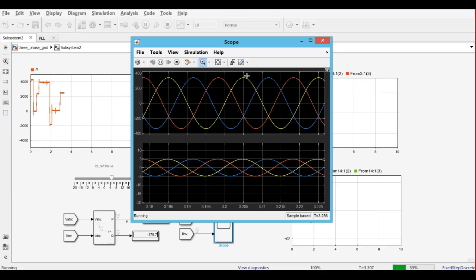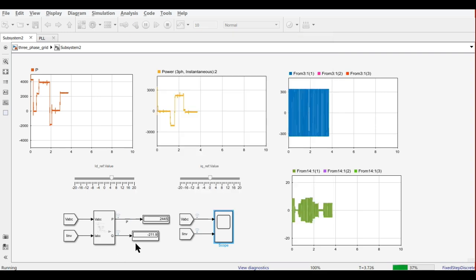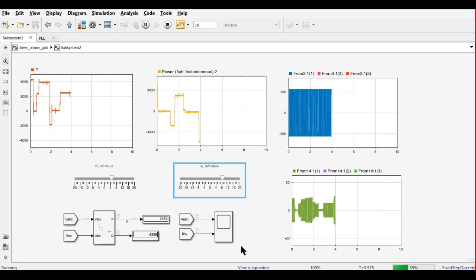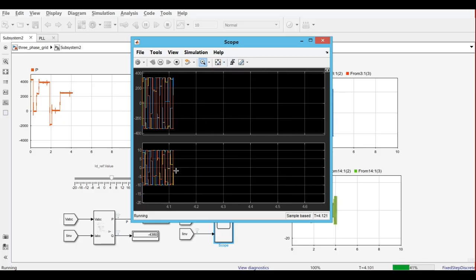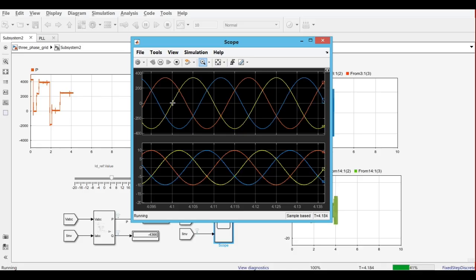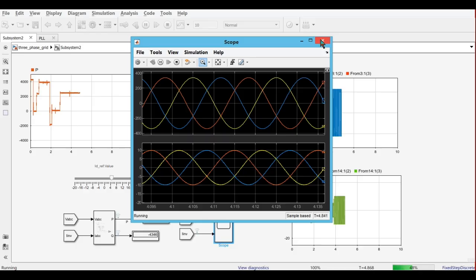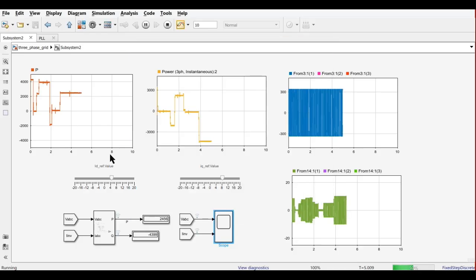We make active power equal to 0 and reactive power equal to 0, then set some active power and observe the phase difference. You can see the yellow waveform — that is V_A — and the inverter current. Both are in almost the same phase. When we change the reactive power, the inverter current waveform lags behind the voltage, demonstrating reactive power control. This is the active and reactive power control using synchronous reference frame theory.